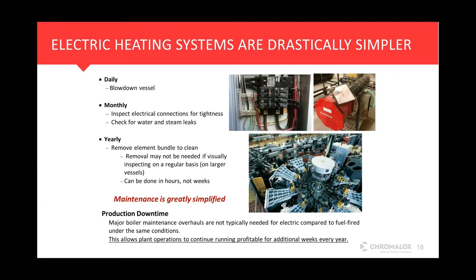When you look at maintenance, electric systems are very simple to maintain and operate. In terms of a maintenance schedule, on the daily side, you have a blowdown. Again, that's not really specific to electric systems, but that is one thing to factor in. So you do need a blowdown vessel. On a monthly level, it's really just inspecting your electrical connections, making sure they're tight. But if we're talking about a medium voltage system, you're only looking at a handful of circuits, such that the time invested in checking those connections is pretty minimal. You also want to check your water and steam leaks. Again, that's not specific to the electric systems, but it is something that gets factored in.